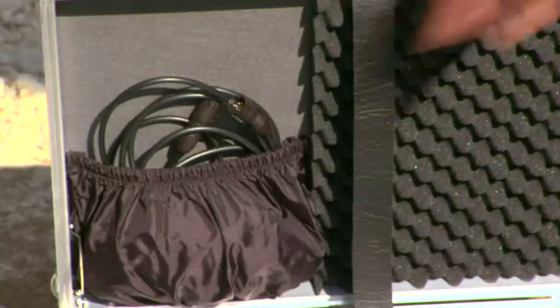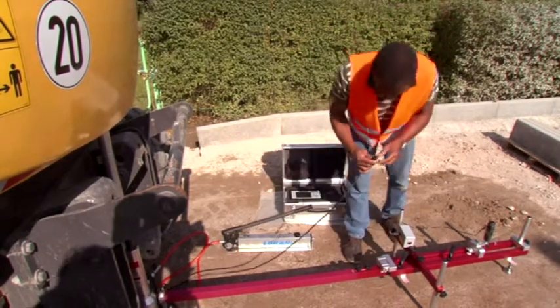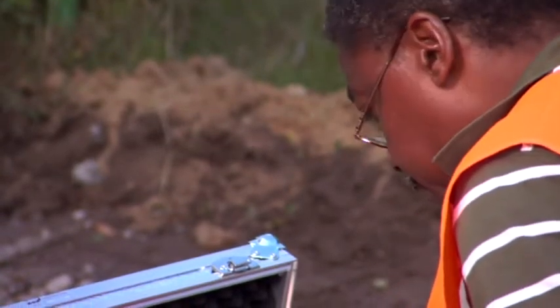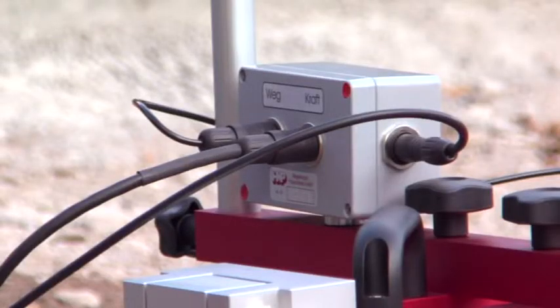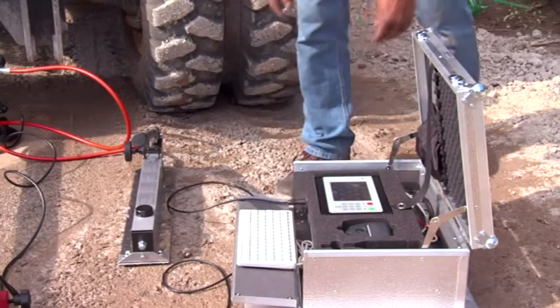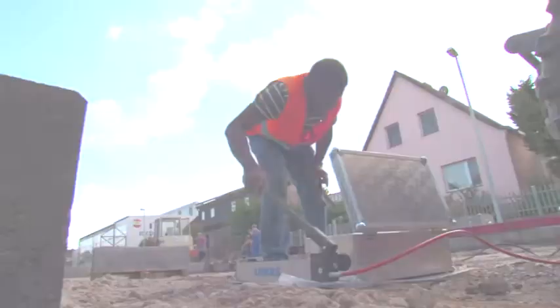An excellent innovation is the use of a specifically designed measuring head, which brings the measurement results for path and force together via the support frame. The measuring head guarantees a digital and interference-free transmission of force and settlement values to the measuring mechanism. In order to simplify the analysis, the respective date, time, and a running number automatically complete the dataset.